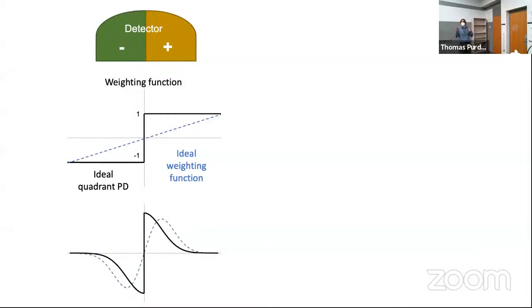Turns out we can improve a quadrant photodetector further with a very simple trick. The idea is that if we wanted to weight where our photons lie on our detector, it turns out the photons that are further away from the center we should weight more. Those have a larger deviation. And it turns out the best way to do things is a linear weighting. What we actually have when you look at a quadrant photodetector is just a step function. If it's on the left, we say -1. If it's on the right, we say +1. We'd actually like to use a linear weighting.